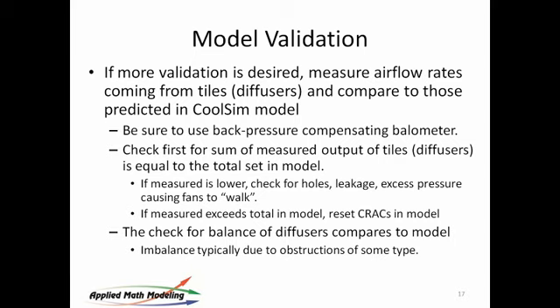And the first thing you want to do is to measure the total output of all of your outlets, diffusers, tiles, and make sure that they match what you've got in your model. And again, back to this issue of walking the fan curve, if what you measure doesn't equal what's being delivered by the spec on the fan, then there's an issue there, right, Liz? I mean, there's a reason why. Yeah. It's usually pressure or belt slippage or age. And if it exceeds the total in the model, then reset the CRACs in the model, because I have seen them go the other way too, where they over-deliver. The specification says 10,000, they measure them, they're producing 12. So there's that case too.